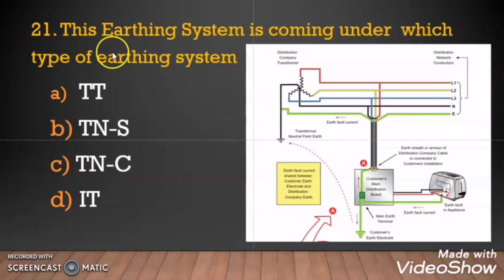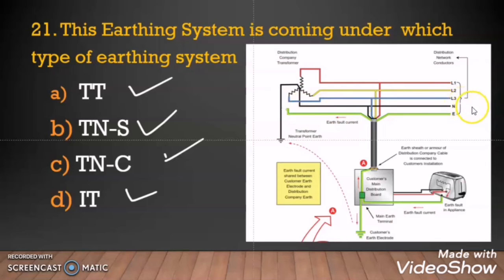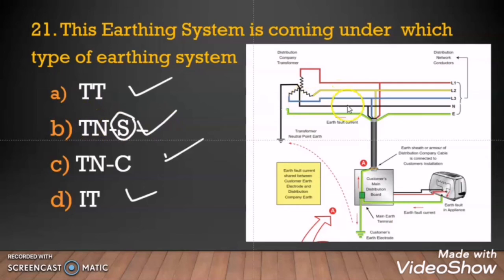Question 21: This earthing system is coming under which type — TT, TNS, TNC, or IT? In this system there is one earth conductor separate from the neutral conductor, meaning neutral and earth are separate from each other. S stands for separate, N stands for neutral, and T stands for terra meaning earth. Since the earth conductor and neutral conductor are separate, this is a TNS system. If the neutral and earth were one conductor, it would be a TNC system.